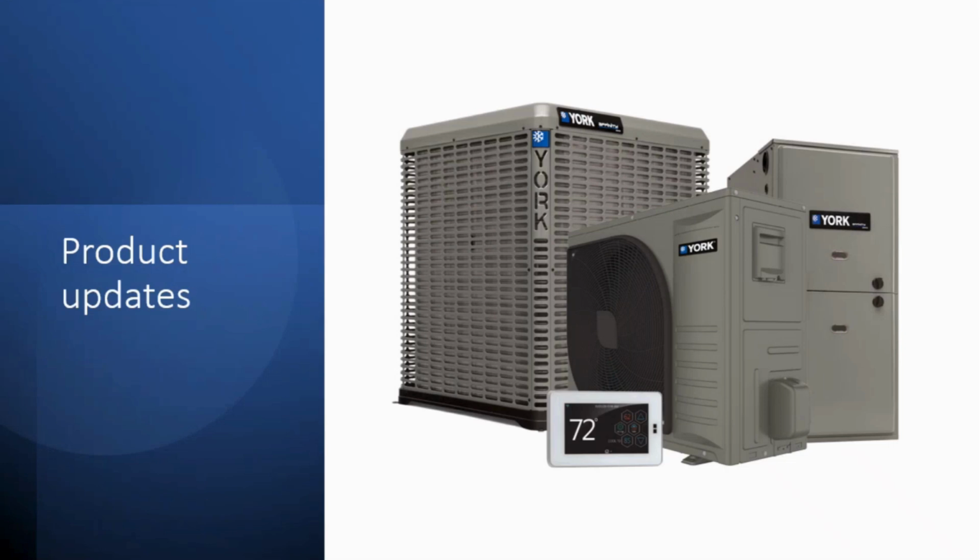Yes. You still need to use the same practices like what we were doing before. If you're changing refrigerants and you're reusing the line set, you should flush it. Now, not necessarily that you have to use R11 every time. If it's basically a straight line shot, flush it with nitrogen and blow out as much oil as you can. However, if you're going to have a spot where you may have a low spot, then yes, you would want to flush that with R11 and follow it up with nitrogen. So the line sets can be reused as long as you flush them out.